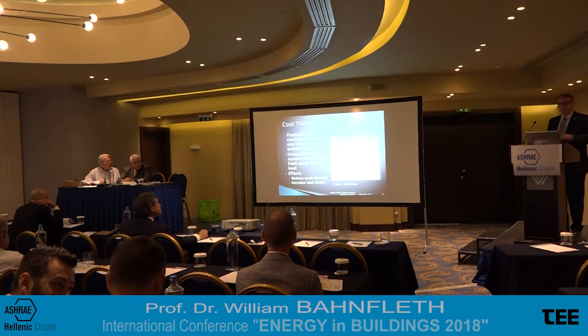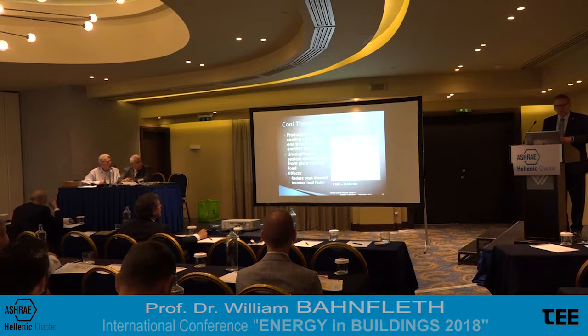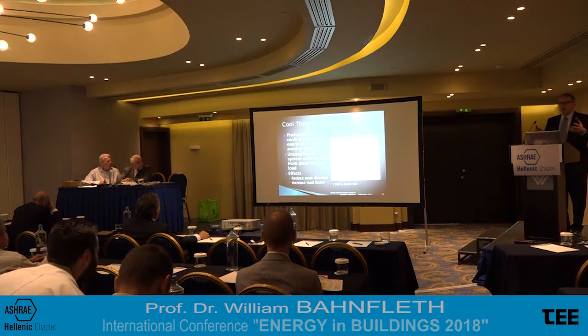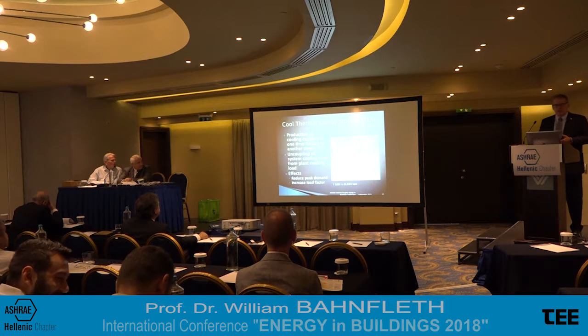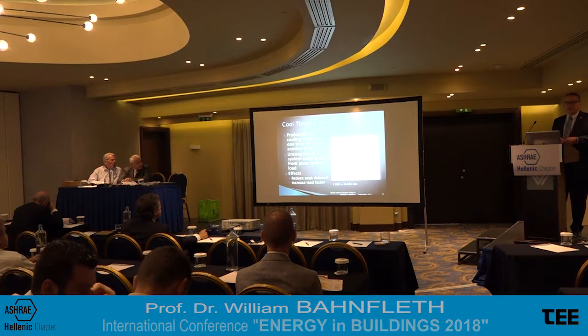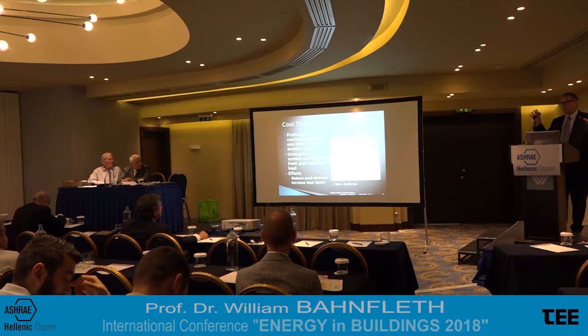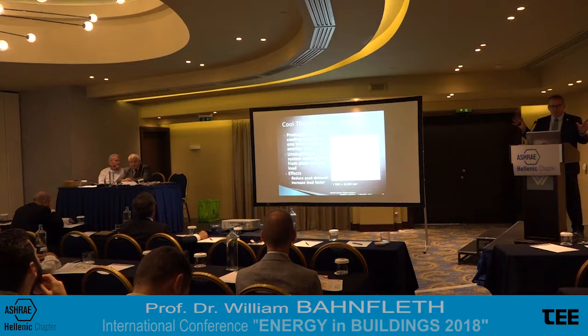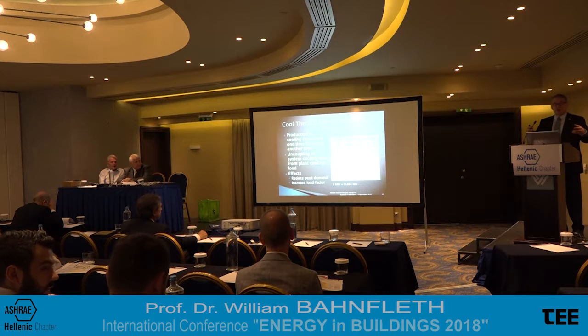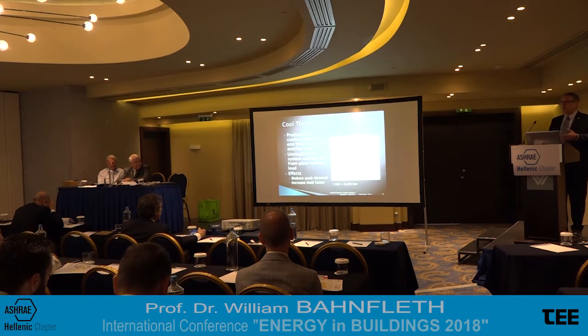So let's move on to thermal storage specifically, and a very brief review for those of you who are not thinking about this frequently. It's simply the production of cooling capacity at one time so that we can use it at another, and the modifications that we make to our mechanical systems to do this essentially separate the shape of the cooling load profile from the shape of the plant operating profile. And so that allows us, if we have enough storage in our system and know how to use it, to optimize both the size and the efficiency of the plant.